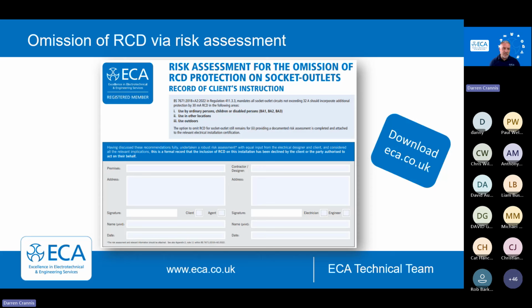Typically, where you might see this is in, for example, food processing plants where conveyor belts might be on commandos to switch them out very quickly for maintenance, or motors, or data centers. So every data center in the UK will have a couple of maybe 32 amp commando sockets for an A/B feed underneath the racks. They will not have 30 milliamp RCD protection. They will be in a controlled environment that's not accessible by ordinary persons. So absolutely, we still do this. It's not a departure, providing it falls into indent 2, and we append this to our electrical certificate, and the client's aware that it's a live risk assessment, i.e. if something changes in their business, they need to review this, not just shelve it.